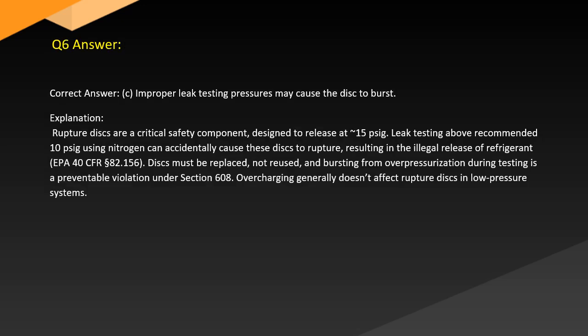Answer. Correct answer: C. Improper leak testing pressures may cause the disk to burst. Explanation. Rupture disks are a critical safety component designed to release at 15 psig. Leak testing above the recommended 10 psig using nitrogen can accidentally cause these disks to rupture, resulting in the illegal release of refrigerant. EPA 40 CFR 82.156. Disks must be replaced, not reused, and bursting from overpressure during testing is a preventable violation under Section 608. Overcharging generally doesn't affect rupture disks in low-pressure systems.